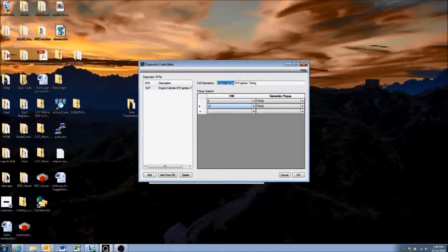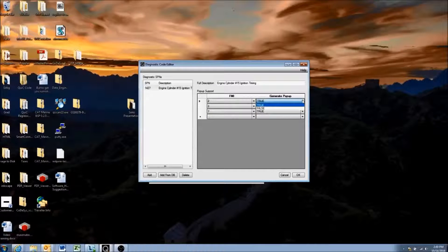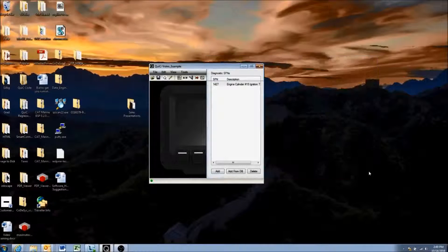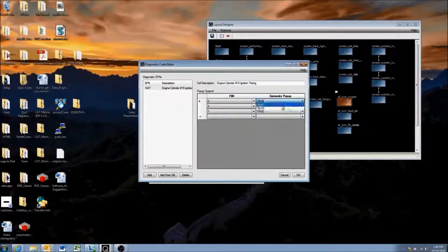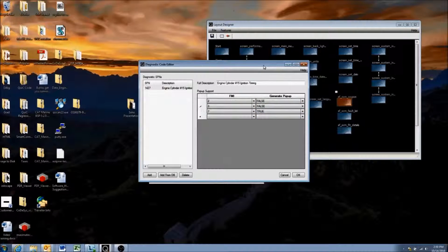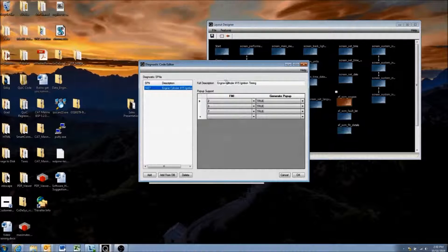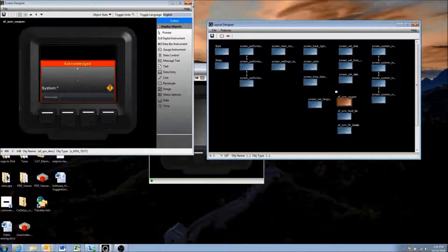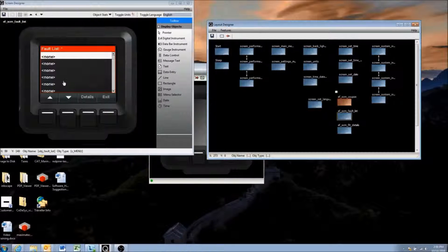We can select different FMIs we want shown to the user — for example, FMI 2, FMI 3, and FMI 7. On the right, we can set whether to Generate Pop-up as true or false for each. If we choose false, no pop-up is shown. If true and the display receives a DM1 or DM2 from SPN 1427 with those FMIs, it will show the pop-up screen. If no pop-up is generated, the fault still appears in the fault list — just without a pop-up.